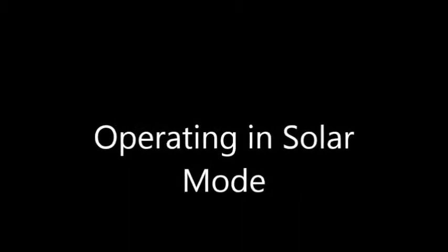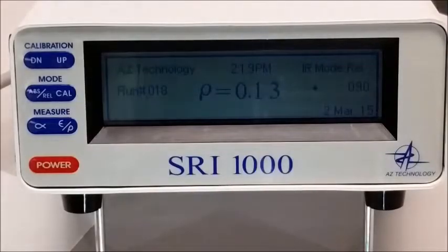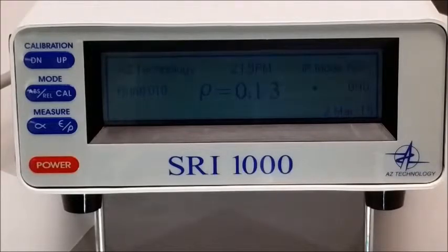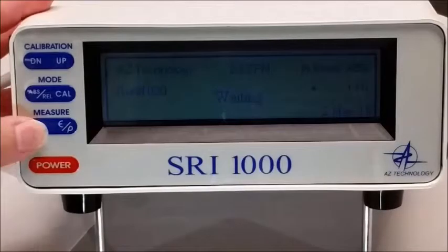Operating in solar mode. Besides the IR reflectance emittance modes of operation, the SRI 1000 can also be used to make solar absorptance or alpha measurements. Unlike with the IR measurements, for solar measurements, a warm-up of only 2 to 3 minutes from a cold start is sufficient. In order to operate the SRI 1000 in the solar absorptance mode, press the head trigger to place the unit in waiting mode and then press the alpha button on the control display unit.